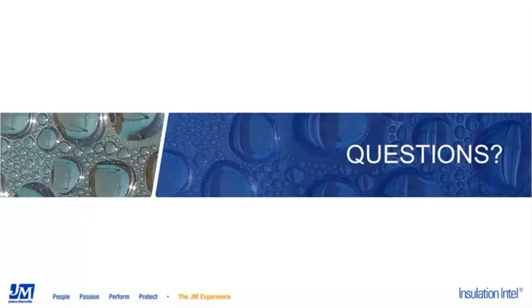All right, thanks, Jim. The next one I'm actually going to direct to you, Jim. That is how to best ensure vapor barriers around items such as hangers, supports, and valve handles. This is a really important question, and it comes back to what Meredith and Kathi were talking about. The continuity of the vapor retarder is critical to the success of the insulation system.